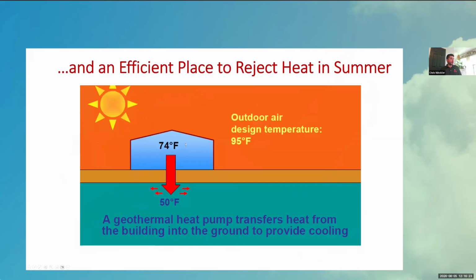Here's the opposite: we're collecting heat from inside the house, even though we're putting cold air into the house. We're taking that heat and moving it through refrigerant into the ground. With an air source or conventional system, to compress and expel that heat into 95-degree air is much more difficult and takes more energy than expelling energy into 50 degrees. That's where we get our efficiency bump—about 40 to 50% higher efficiency doing air conditioning with a ground source system than an air source system, since it has to work less hard. Same technology, we're just dumping that energy into 50-degree earth that accepts it much easier.